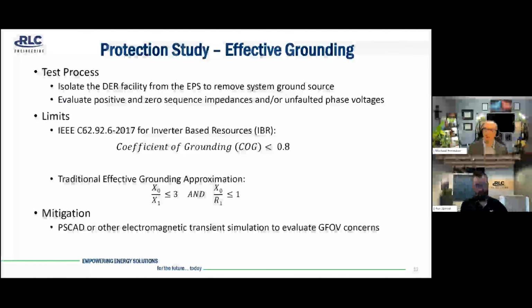But for effective grounding, we will typically isolate the DER facility, which removes the ground source, and then we evaluate positive and zero sequence impedances or unfaulted phase voltages if we're looking at the coefficient of grounding methodology. The coefficient of grounding method is typically used for systems with a lot of inverter-based resources. The traditional method looked at zero sequence reactance to positive sequence reactance and zero sequence reactance to positive sequence resistance. If there are concerns about GFOV, we'll typically look at this in PSCAD or EMT simulations, and it's a good way to confirm the size of any effective grounding devices that we might need to add to the system.